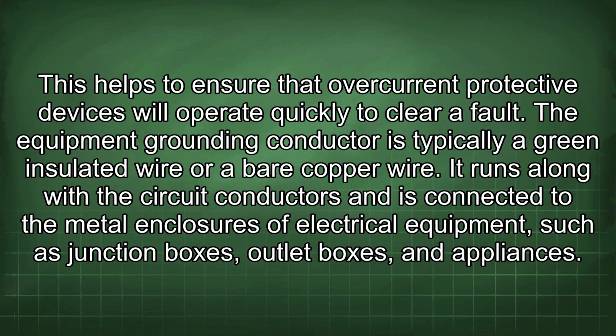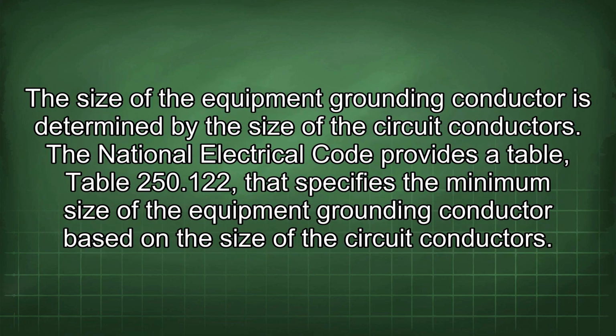The equipment grounding conductor is typically a green insulated wire or a bare copper wire. It runs along with the circuit conductors and is connected to the metal enclosures of electrical equipment such as junction boxes, outlet boxes, and appliances. The size of the equipment grounding conductor is determined by the size of the circuit conductors. The National Electrical Code provides a table, 250.122, that specifies the minimum size of the equipment grounding conductor based on the size of the circuit conductors.